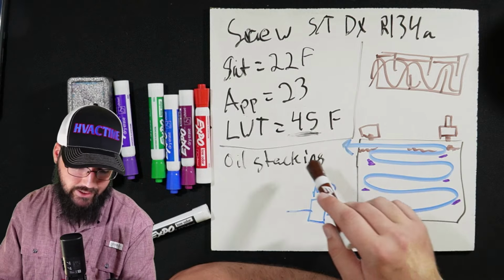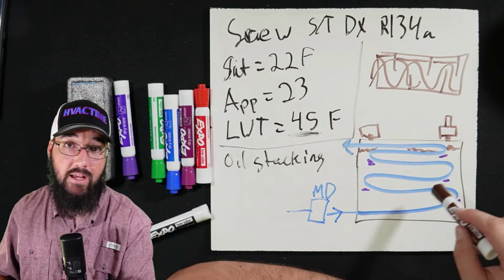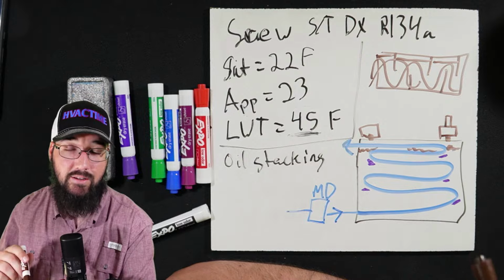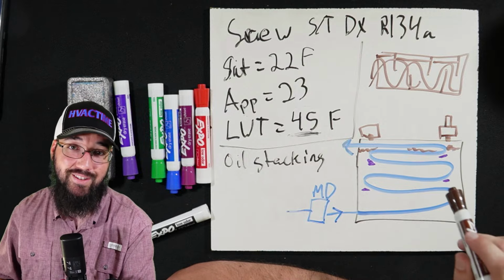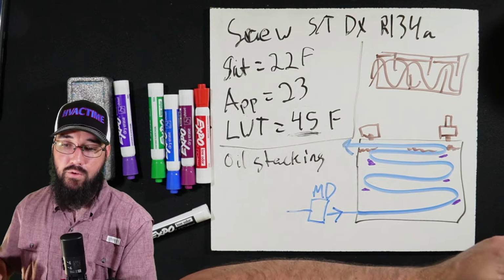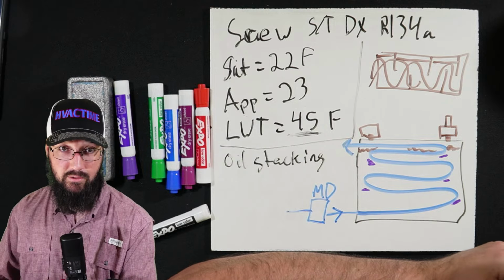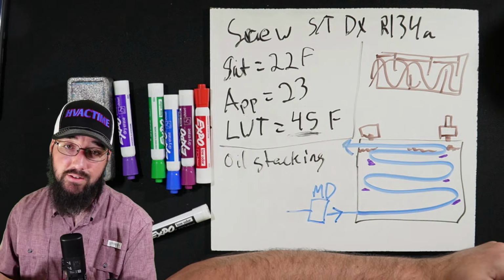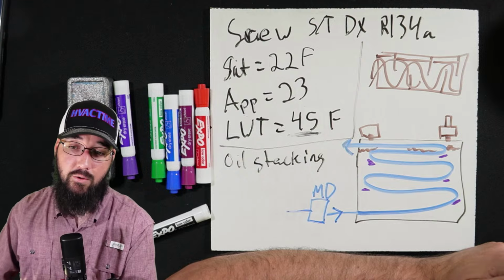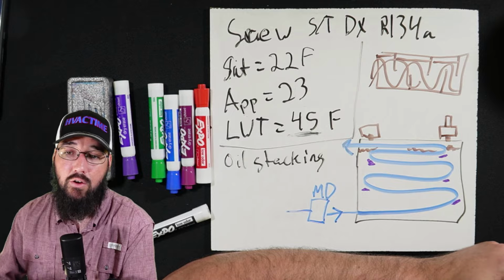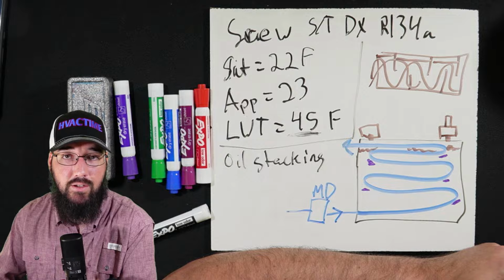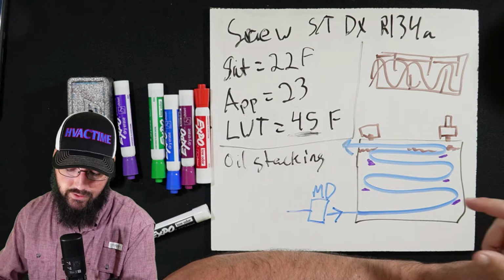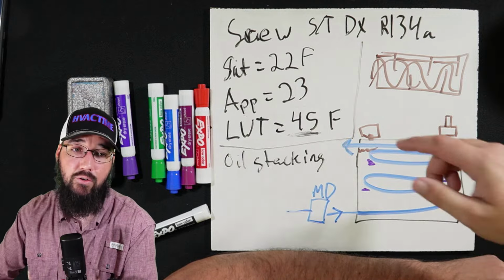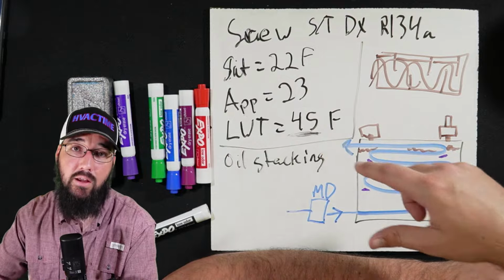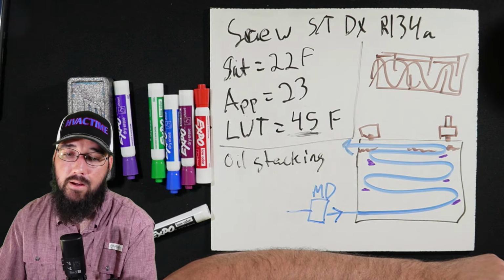Could be air stacking, could be possibly oil stacking. If it is oil stacking, again, that's going to be from a low load over an extended period of time. So either increase load, that is the best thing in my opinion. Just get the load up on that machine. As it loads up, it's going to increase the velocity through the circuit. That higher velocity is going to allow that oil to return back. You're going to see these numbers improve with runtime.